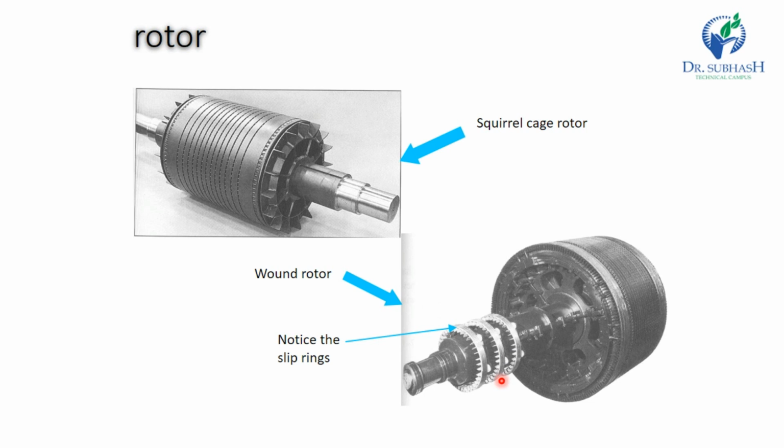When running under normal conditions, the slip rings are short circuited by a metal collar which is pushed along the shaft and the brushes are lifted from the slip rings. This is done to reduce frictional losses and wear. As a regular three-phase winding is used for the rotor, this type is called a phase wound rotor type, and it's also called a slip ring type motor.